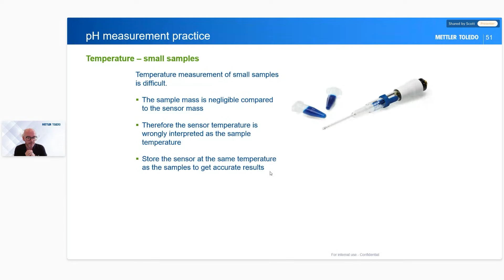But say, for example, these tubes are at 37 degrees, then if you introduce your electrode at room temperature, it would change the temperature of your sample. So what you need to do is heat your electrode in some storage solution at 37 degrees. So when you introduce the electrode into a very small sample, they're both reading the same reading. So it's something to take account of when you're taking temperature measurements with very small samples.